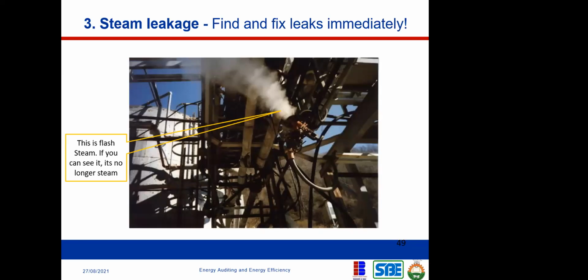I've talked about this. Now this is a steam leak. So when you see this kind of thing, just know that it's a waste of energy, right? When I talked about flash steam, this is what it looks like. When steam suddenly expands, it begins to condense very rapidly into water. Then you see a mixture of steam and condensate, because ordinarily you cannot see steam. Steam is invisible. But if you can see it, it is no longer steam; it is now flash steam, which is what I try to explain here.